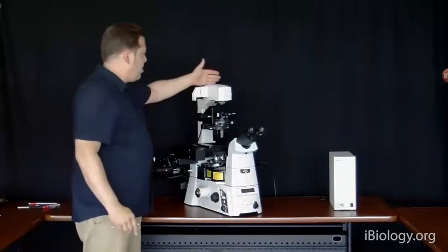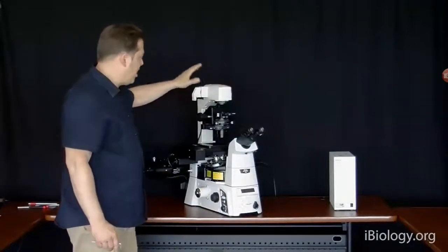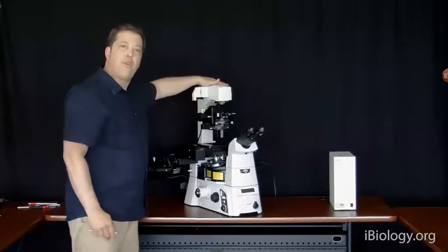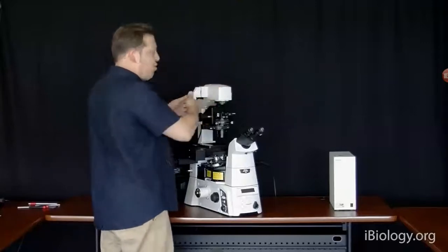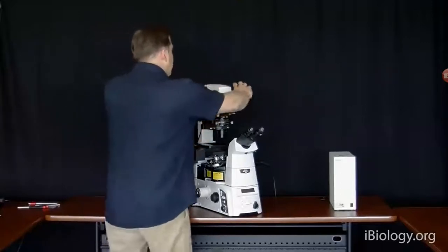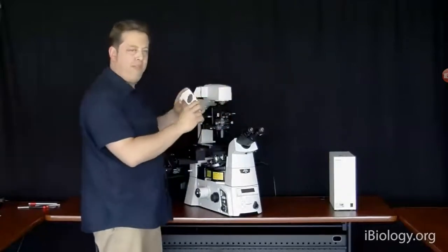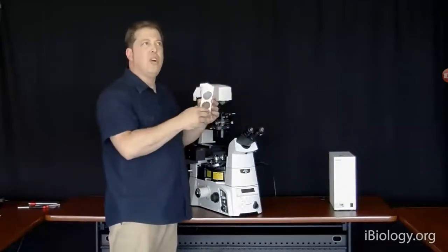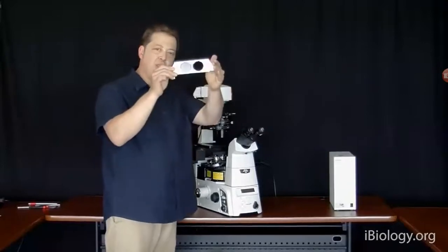So next, transmitted light comes through here. This is all aperture space. There's nothing in focus in there, and that's why we put our filters in this location. We've got several filters and a diffuser in this microscope. Anytime you have a halogen bulb or a bulb with a filament, we normally want to soften the edges of that sharp filament. We use what's called a diffuser.